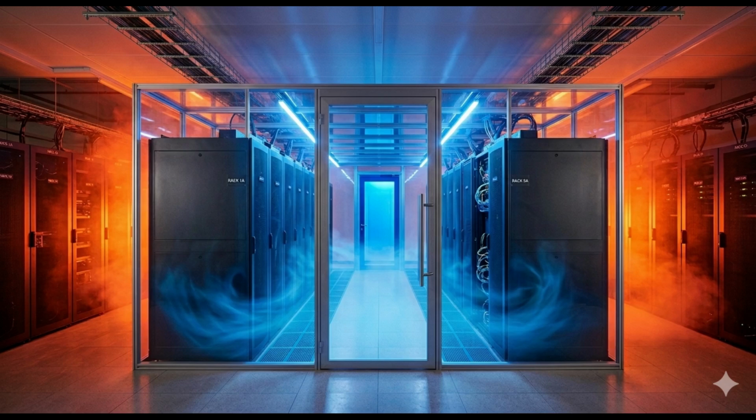Let's run a calculation example. Sure, let's say we have a fixed heat load of 100 kilowatts. Okay, 100 kilowatts. Scenario A, we operate with a low delta T of 10 Kelvin. The air goes into the servers at 20 degrees Celsius and comes out at 30 degrees. To remove that 100 kilowatts with only a 10 Kelvin spread, the formula says you need a volume flow of about 30,000 cubic meters per hour. 30,000 cubic meters per hour. That's a lot of fan power.